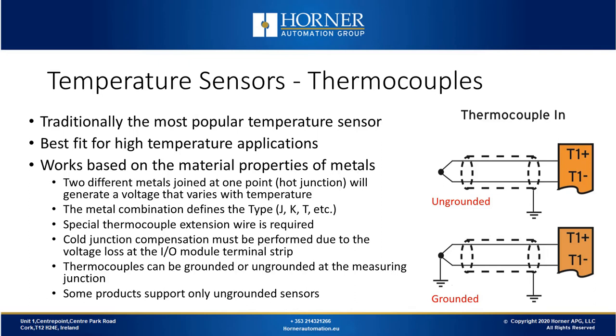Let's take a look at temperature sensors, starting with thermocouples. Thermocouples are traditionally the most popular temperature sensor, although they're not as frequently used today as they once were. They're the best fit for high temperature applications — they can work at thousands of degrees. They work based on the material properties of metals. When you take two different metals and join them at a point called the hot junction, a voltage is generated that varies with temperature. The metal combination used in the sensor defines the type — for example, type J, type K, or type T. When you use thermocouples, you have to use special thermocouple extension wire and have a temperature sensor built into the circuit board where the thermocouple wire plugs in, because you're going to have voltage loss that must be predicted and accounted for.